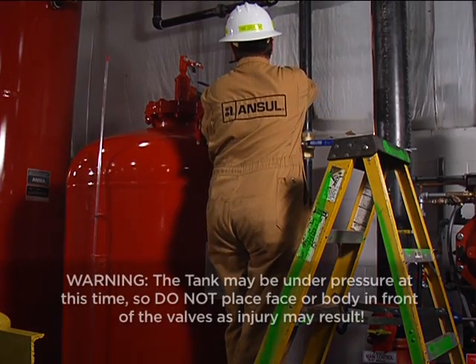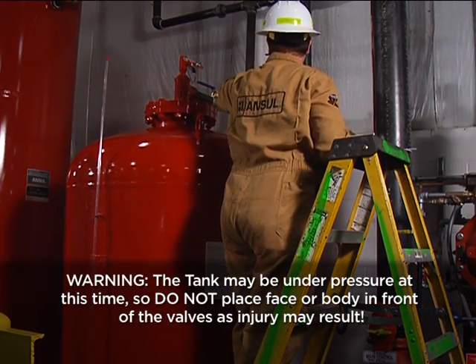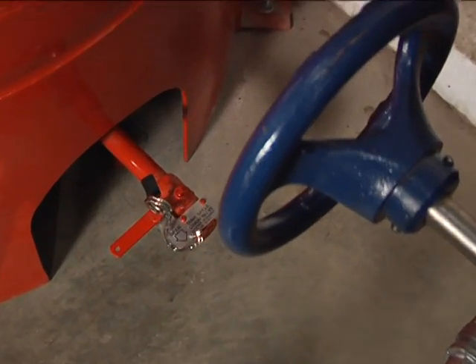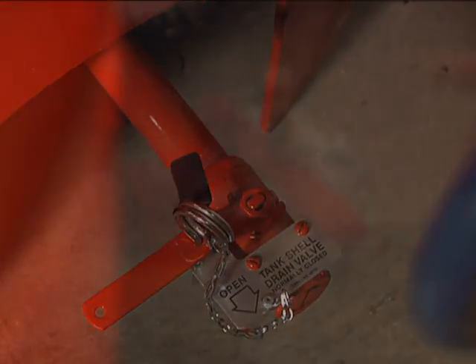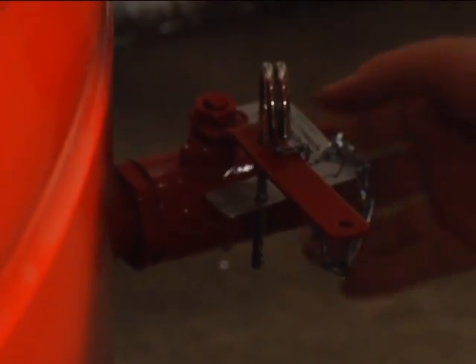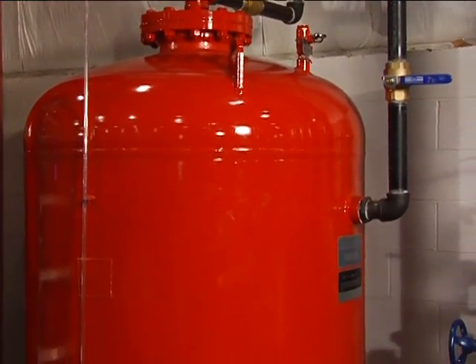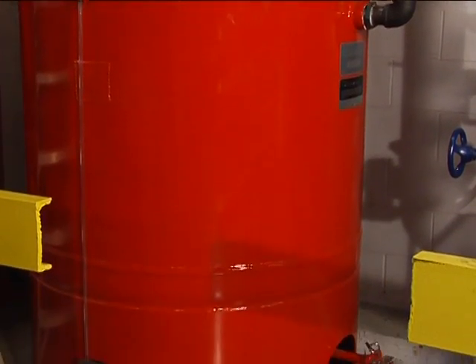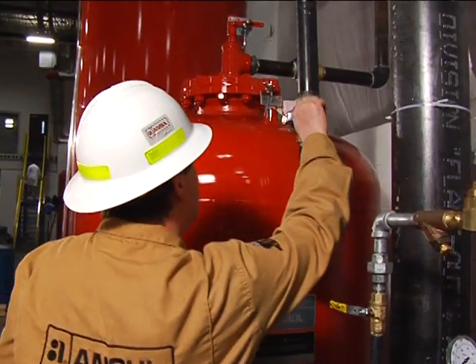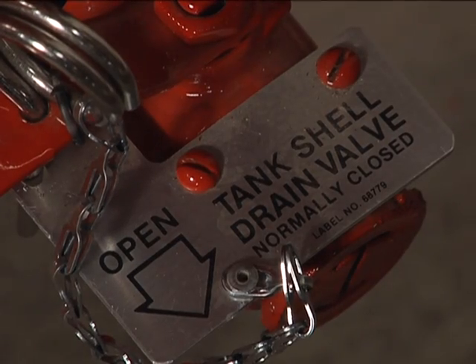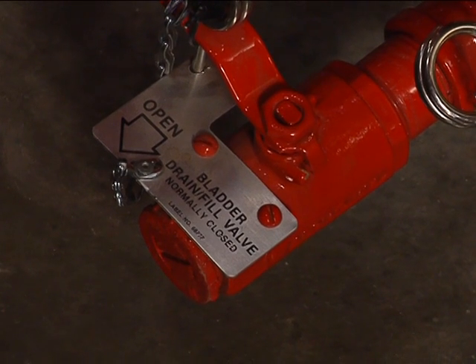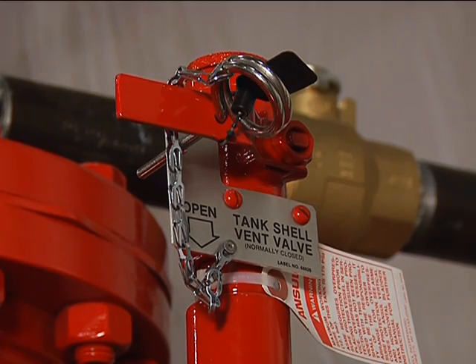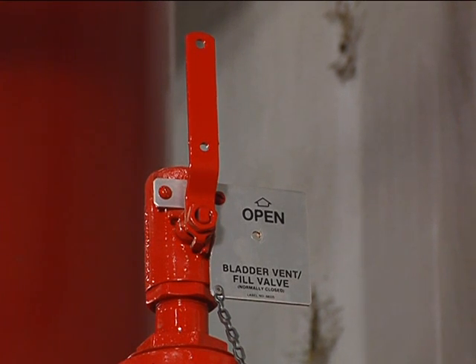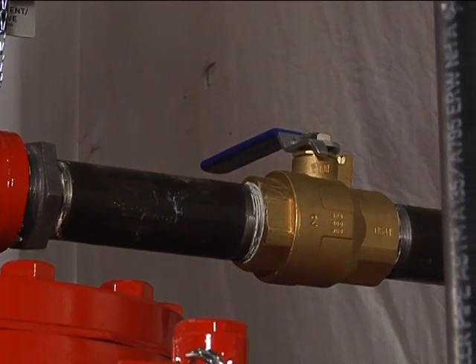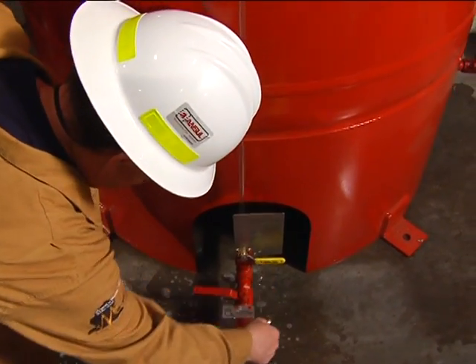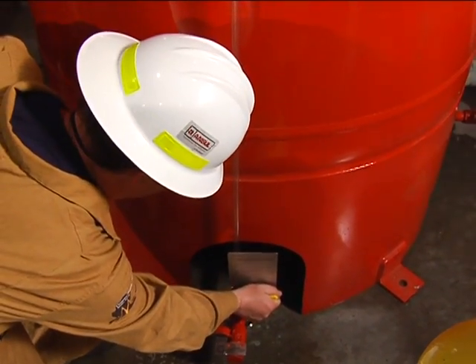Next, slowly open the tank shell vent valve to relieve the water pressure. Now open the tank shell drain valve until all of the water is drained and all pressure is relieved from the tank. Once the water has drained from the tank, place the bladder tank valve handles in the following positions: water inlet valve, closed; tank shell drain valve, closed; bladder drain fill valve, closed; tank shell vent valve, closed; bladder vent fill valve, open; concentrate isolation valve, closed; and, if provided, sight gauge valve, operating.